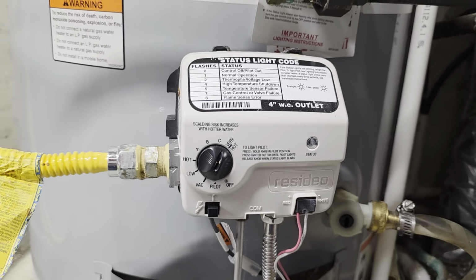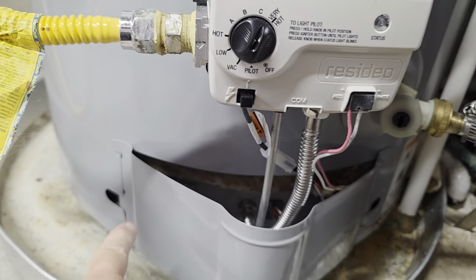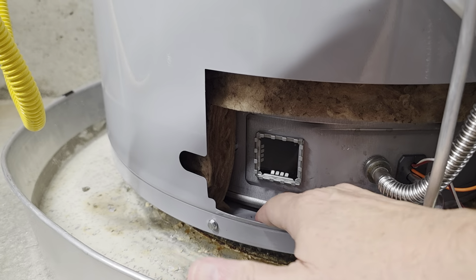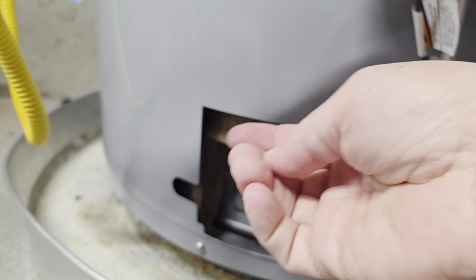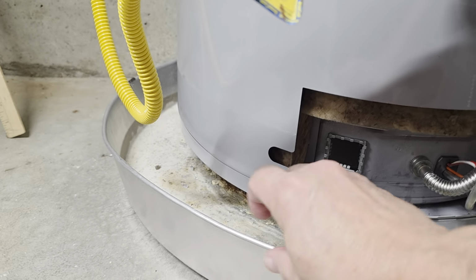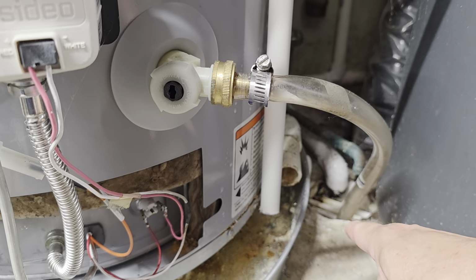Now, what is the problem with water heaters and sediment? Well, there are a couple of problems with them. Number one, you have what is known as condensation buildup, and you have to look down here and you can see what would appear to be rust. So in this case, we are actually looking at a clean environment. We want it to be water free, but when you start to discover water, you have to worry a little bit about that. Now here, this is a catch pan designed to help track the water and push it over to the drain valve here.